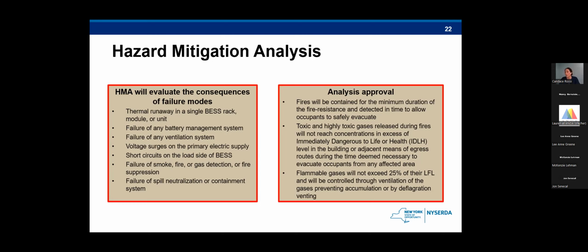So you have thermal runaway in a single rack, module or unit, failure of any battery management system, what happens if there's failure of a ventilation system, what if there's a voltage surge on the primary electric supply, what if there are short circuits on the load side of the storage system, what if there's a failure of the smoke, fire, or gas detection or fire suppression, or the failure of a spill neutralization or containment system.